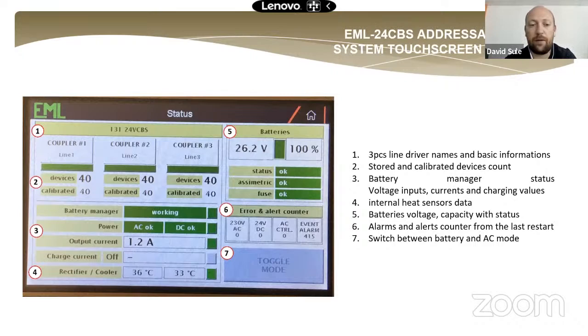We have to check the line driver. Maybe something happened with the cabling, or the line driver has some communication damage. So from here, we can read how many devices we have in the system and how many lights are fully calibrated. We can check the current status of the power. AC 230 is okay, DC 24 volt is okay. How much is the output current?